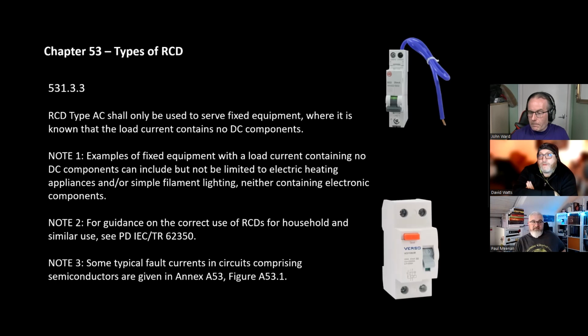Carrying on with that, regulation 53133: RCD type AC shall only be used to serve fixed equipment where it is known that the load current contains no DC. So if you go to your granddad's shed and he's got one of them old bar heaters, AC RCD all the way. Anything else, even this new Lot 20 heaters with their little electronic digital programmers, forget about it. So by default, you can now see the official clear journey that AC RCDs will just be phased out.